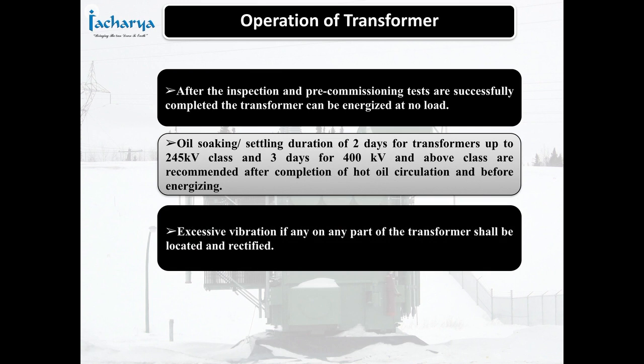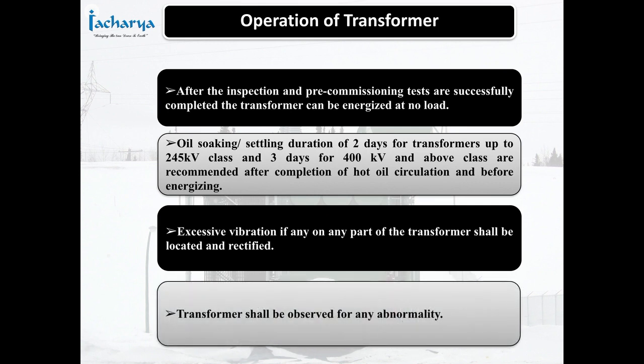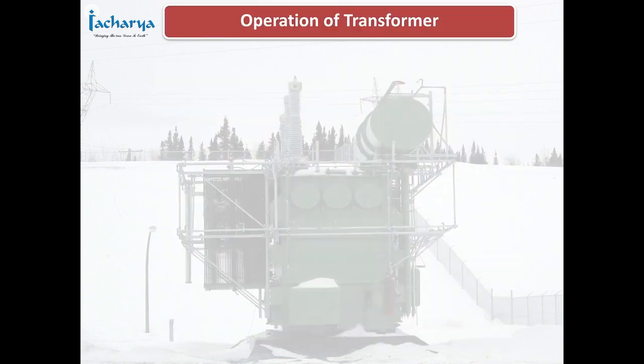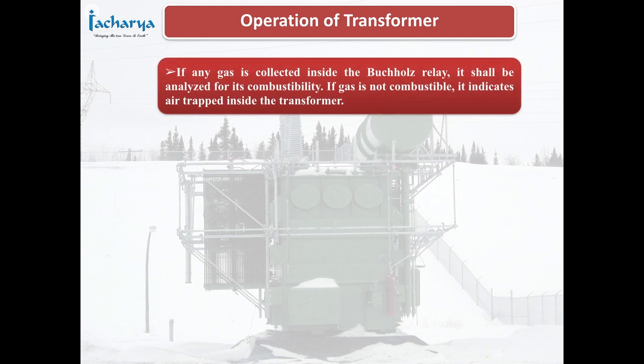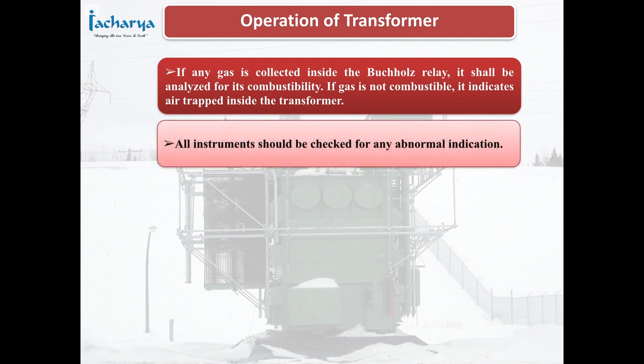Excessive vibration, if any, on any part of the transformer shall be located and rectified. Transformer shall be observed for any abnormality. If any gas is collected inside the Buchholz relay, it shall be analyzed for its combustibility. If gas is not combustible, it indicates air trapped inside the transformer. All instruments should be checked for any abnormal indication.